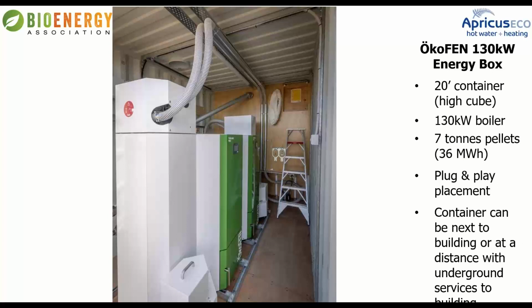No boiler will take potable water. So you would have to have a cylinder if you're doing domestic hot water, and that has a coil inside it to transfer the heat, or an external plate heat exchanger. But if it's circulating water in a heating system that's going into radiators or underfloor or any other kind of emitter, air handlers, fan coil units, whatever, then it just goes straight out of the boiler and round the circuit.